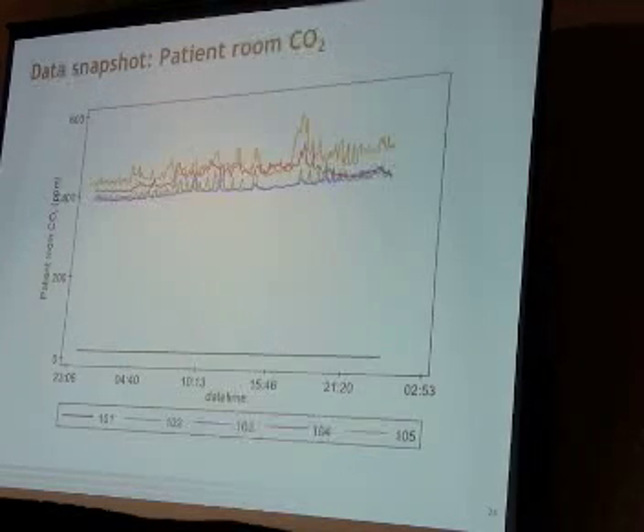Here's a good example of patient room CO2 in these same rooms on the same 9th floor. Another 24-hour sample, 5-minute intervals here. We see differences in absolute magnitude, say between the orange and red, those couple of rooms relative to the green and blue. They're tight, so they're near instrument uncertainty, and that's another story. But what this does show us is that there might actually be greater occupancy in those top two rooms, because their ventilation rates are the same, more or less, since they're controlled by the same system.